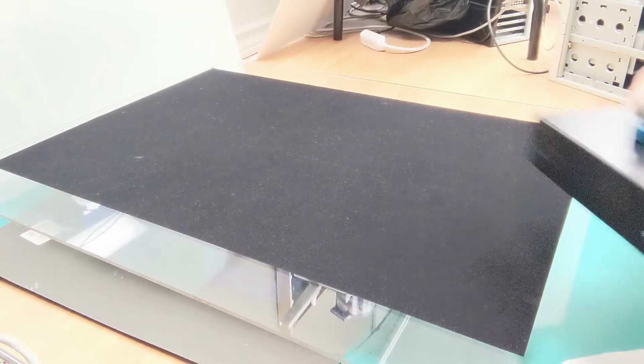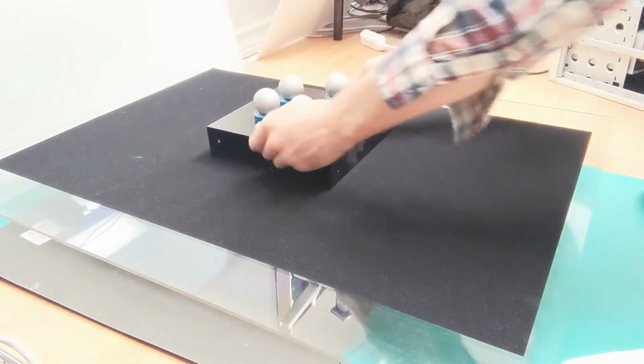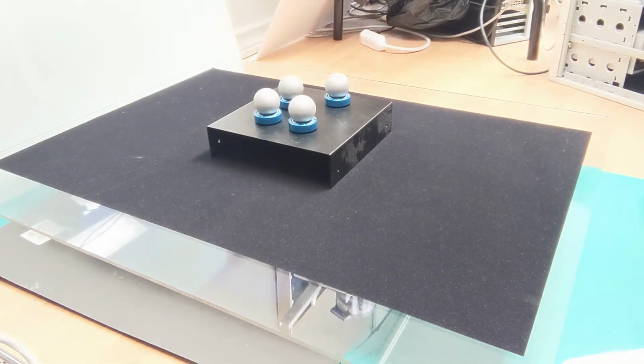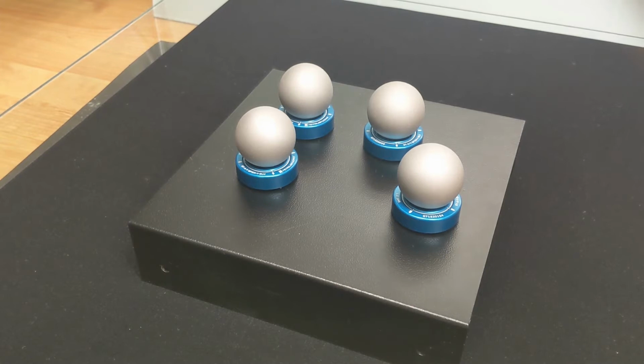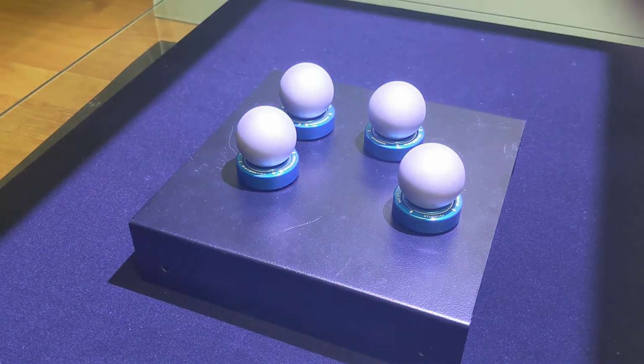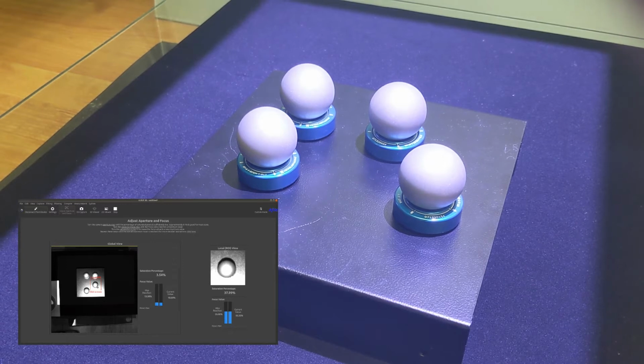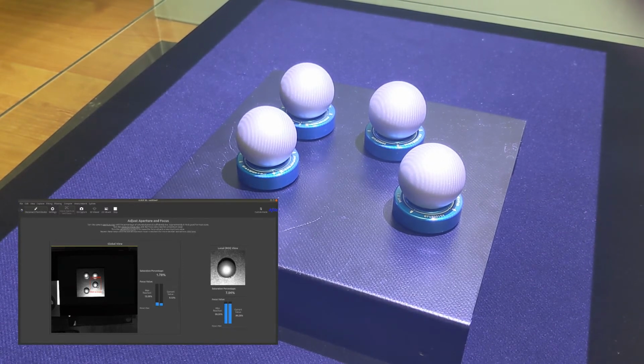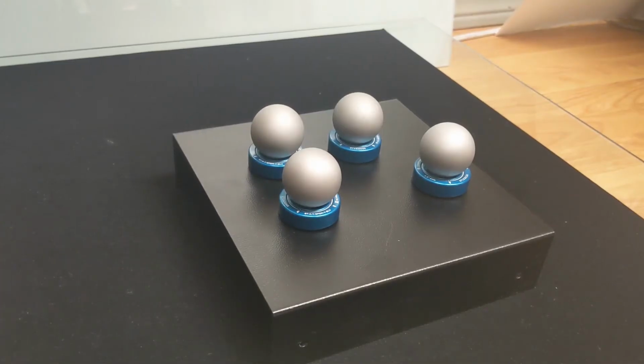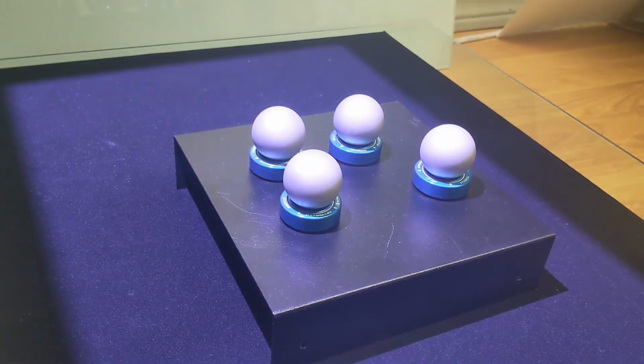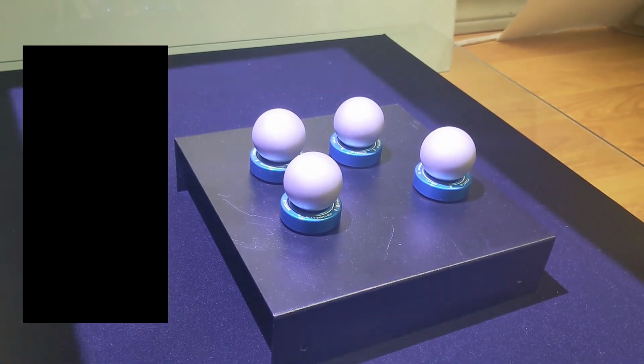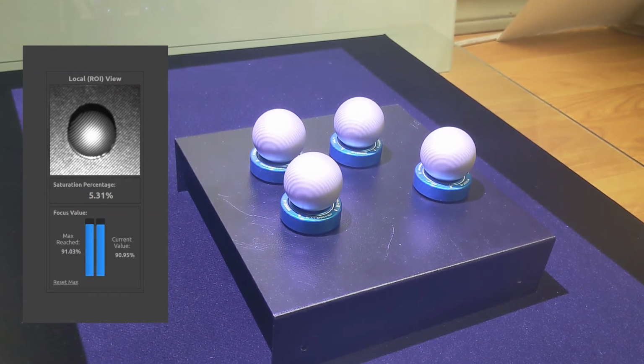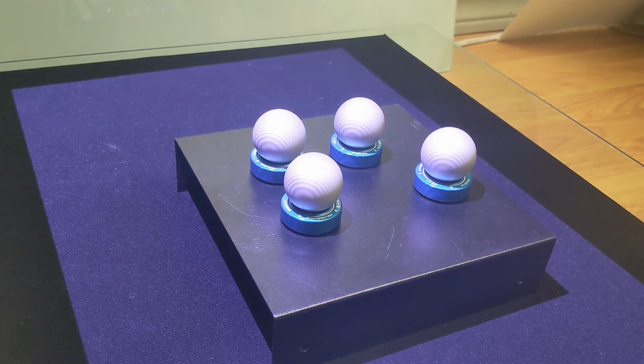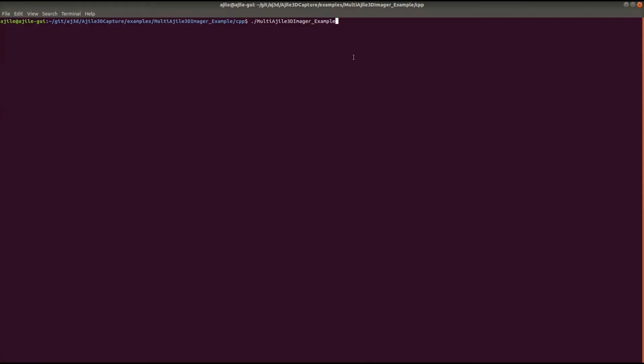Now we'll place our calibration artifact in the working area. We're using 4 reference spheres for this calibration. Now we'll set the focus and aperture for each scanner. For best results, we recommend doing these one at a time within the Ajile 3D GUI. Now that both scanners are in position and focused, close the GUI and open a command prompt.